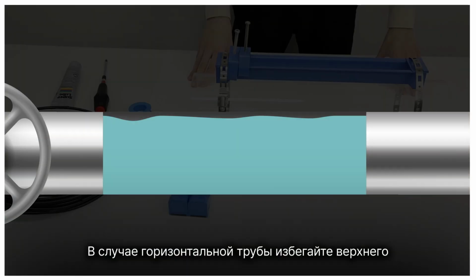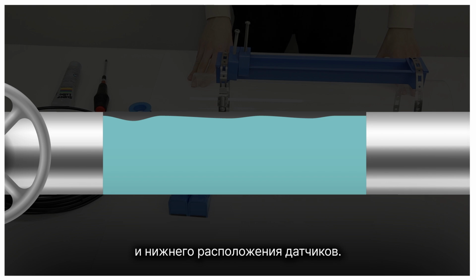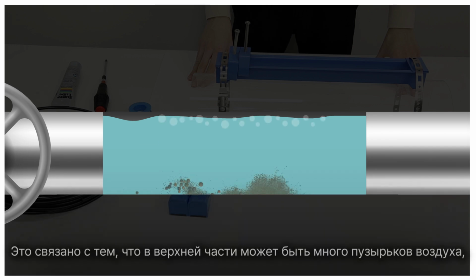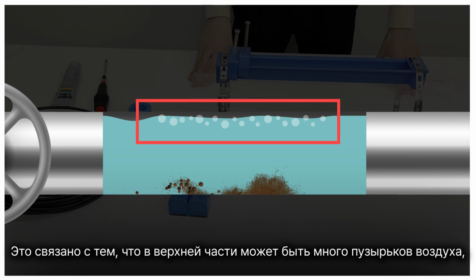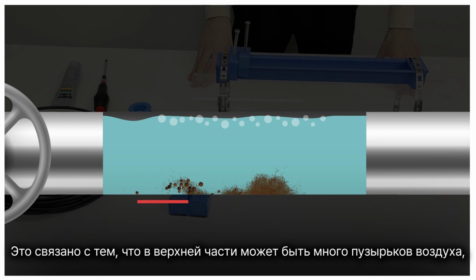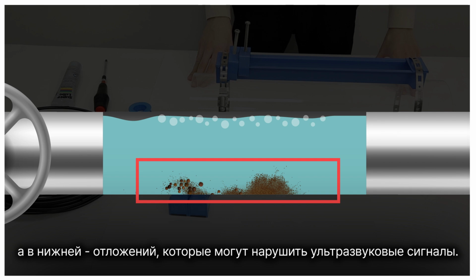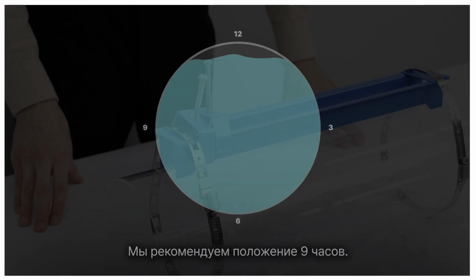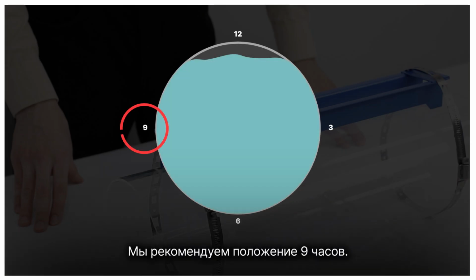In the case of a horizontal pipe, avoid the top and bottom positions for the transducers. That's because the upper part is likely to have lots of air bubbles and the bottom part is likely to have sediments, which could disturb the ultrasonic signals. We recommend the 9 o'clock position.